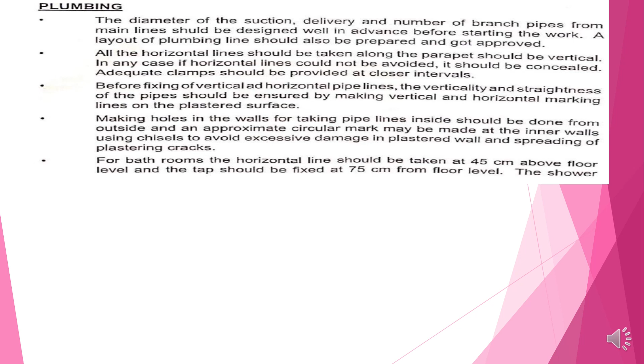For the bathroom, horizontal pipes should be taken 45 cm above floor level and the tap should be fixed at 75 cm from the floor level. The shower point should be fixed at 2.10 meters above the floor level. The pipeline at the toilet should be taken at 45 cm above floor level and fixed at the same level.